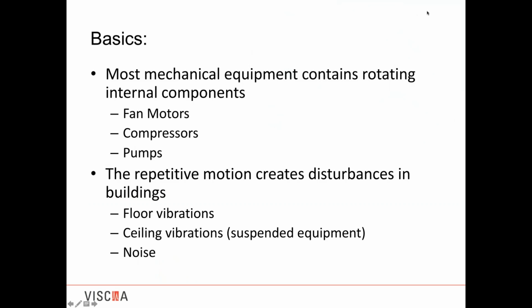First, as the basics, most mechanical equipment contains rotating internal components. And you're familiar with them, I'm sure. Motors, compressors, pumps, basically anything that has an RPM or has cycles, it's going to be vibrating. It's going to create some sort of vibration energy that can get into the building through the floors and the ceiling. Also, it will create noise. And in general, you'll know the equipment might have fan blades, and the fan blades in particular make noise, but they're driven by the motor. So if we isolate the motor, you prevent that energy from going into the building. The compressors will also move liquid, and the pumps will move liquid through the building. Those also become vibration issues.